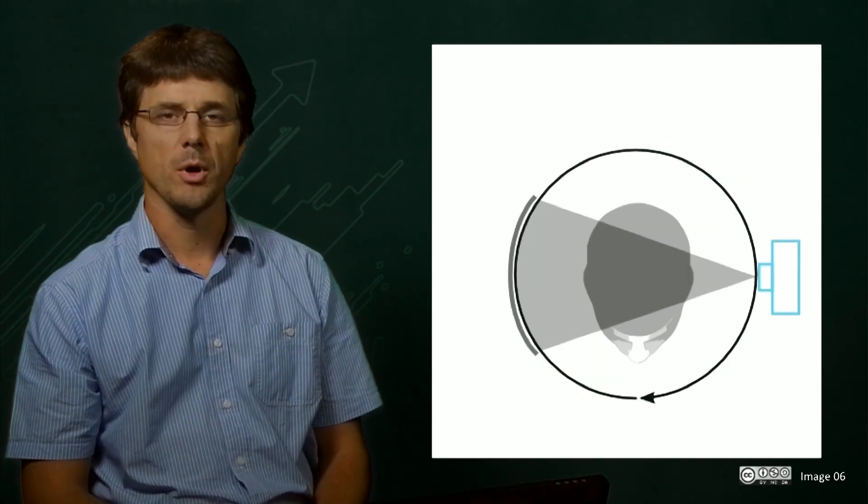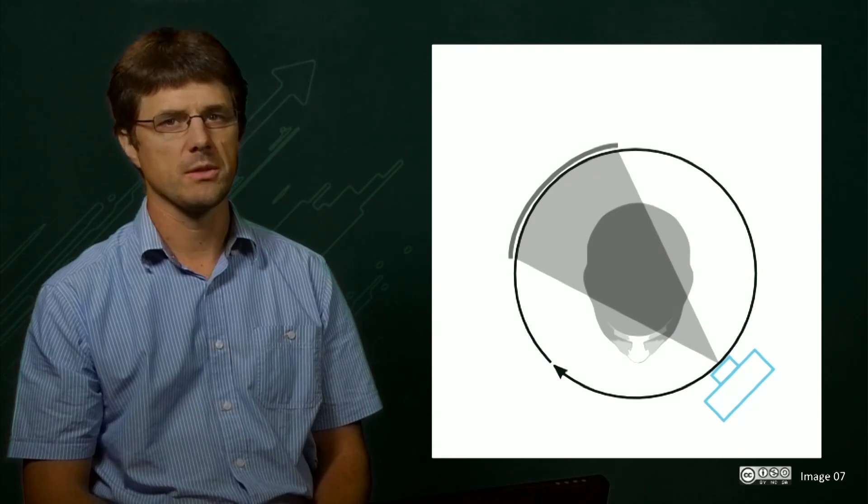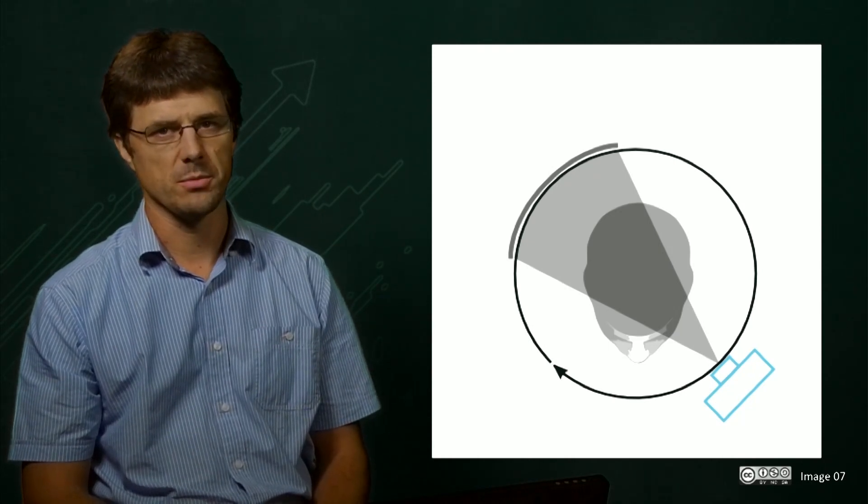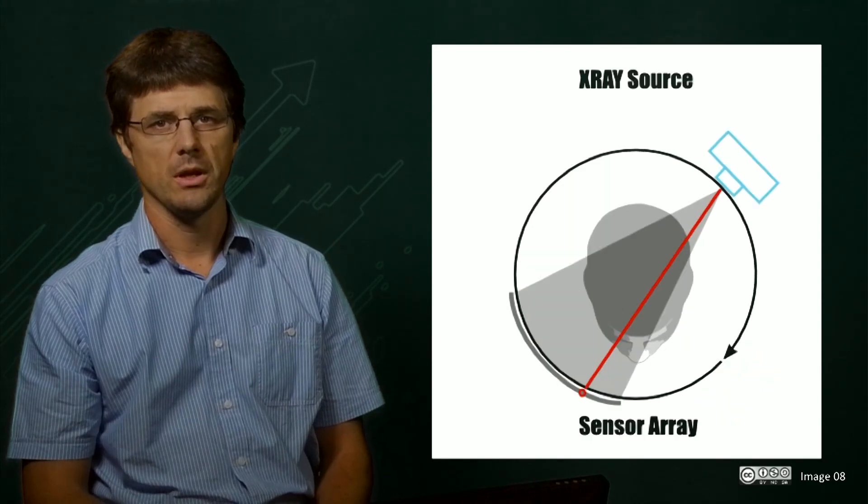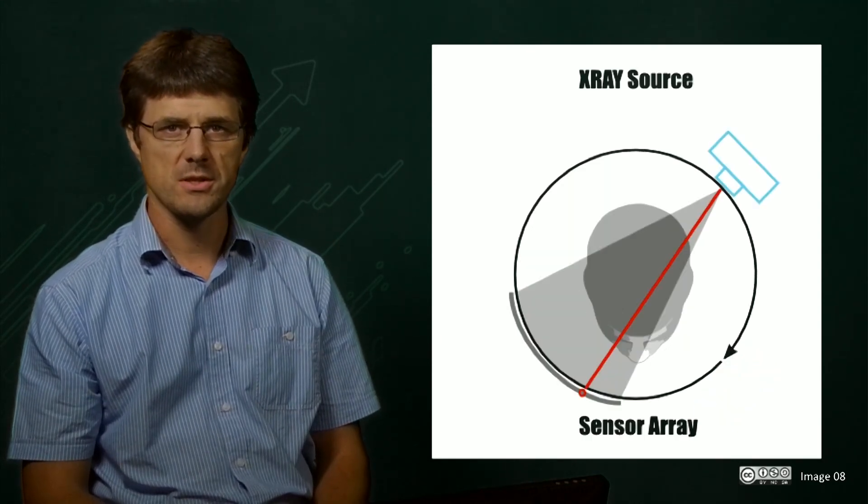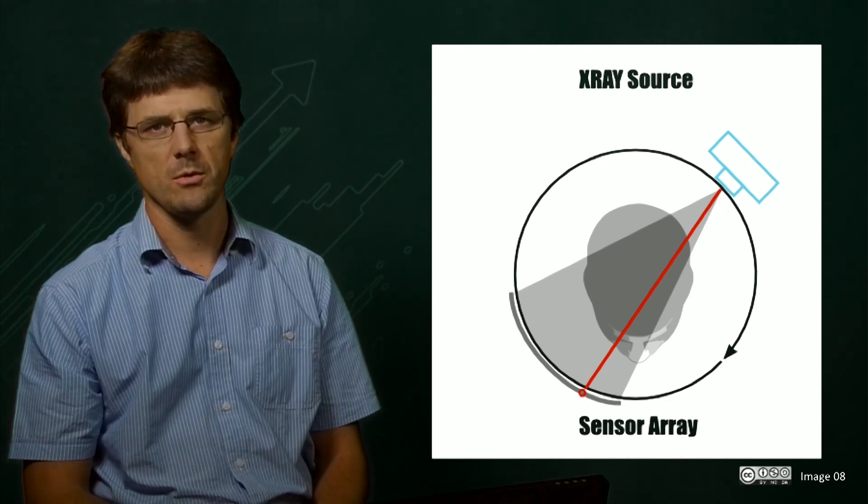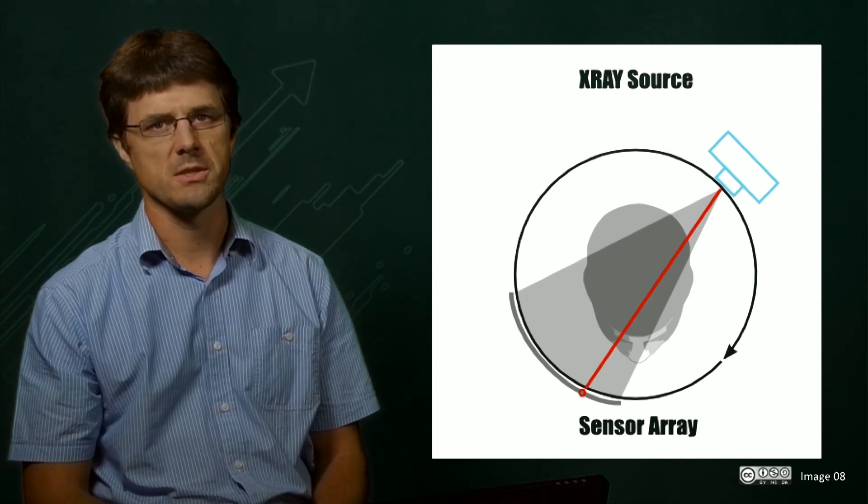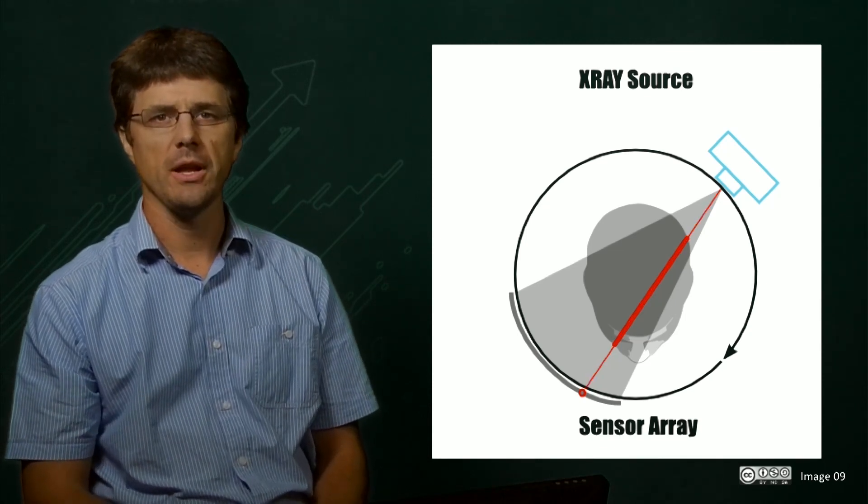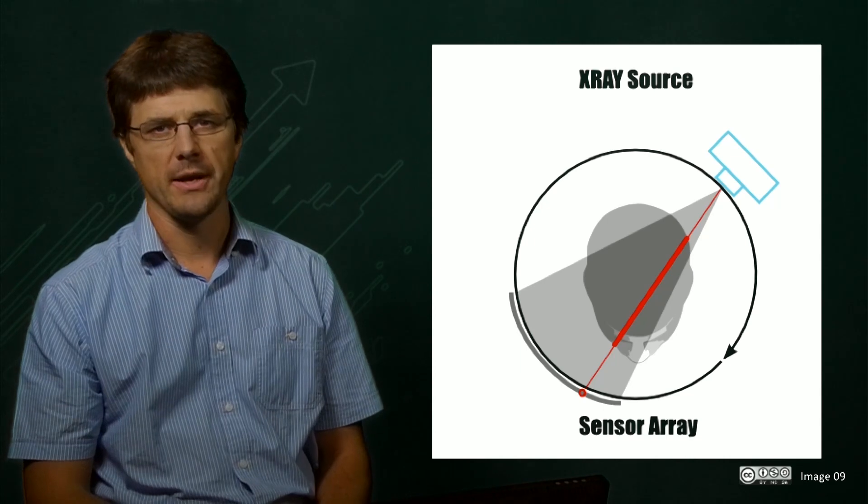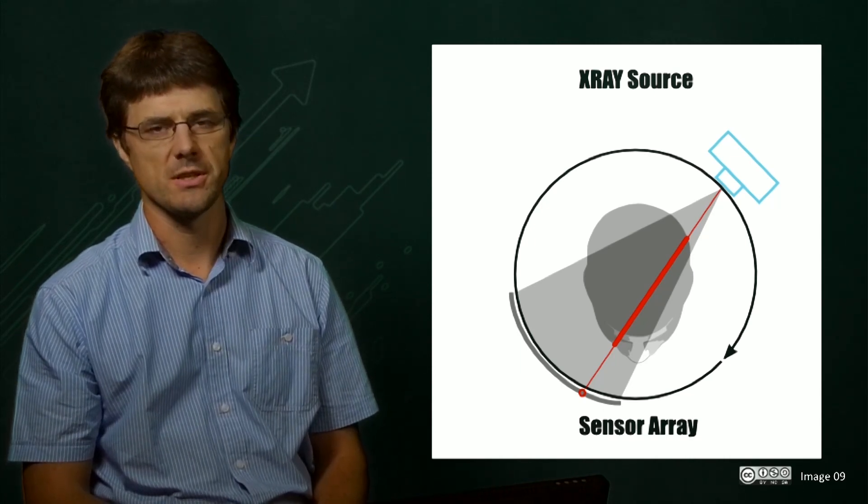As the gantry rotates, multiple projections are then taken. In our case, we will base our examples on four projections for simplicity, even though this number is very low. It is important to remember that the value the sensor will see at the red circled point is the sum of the attenuation that beam will experience as it passes through tissue. This single number is the only output data recorded, and as such, each projection will be a linear series of numbers across the sensor array.